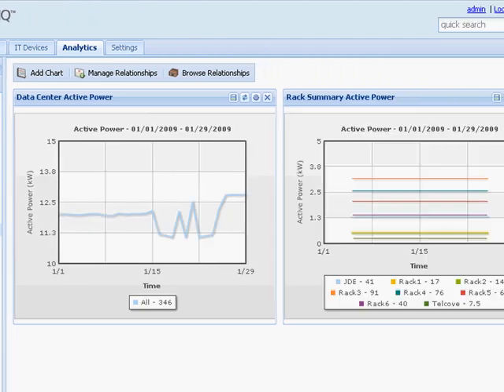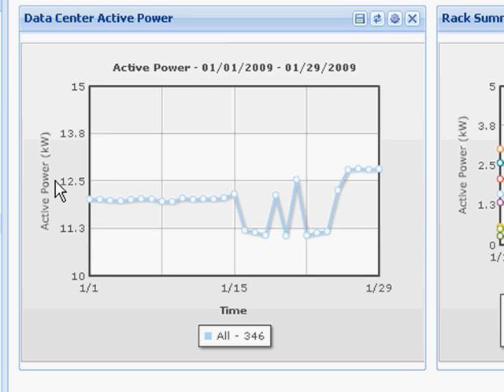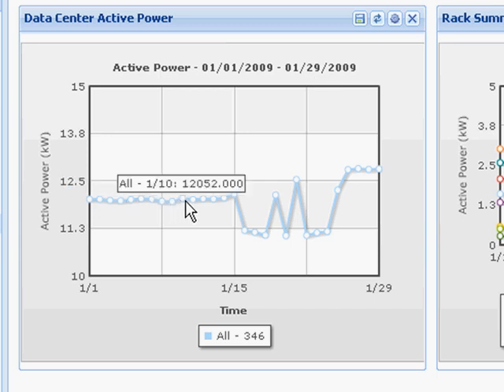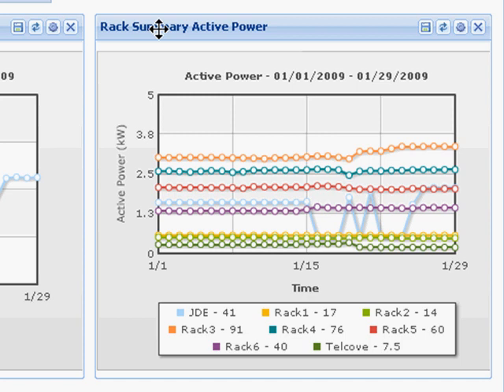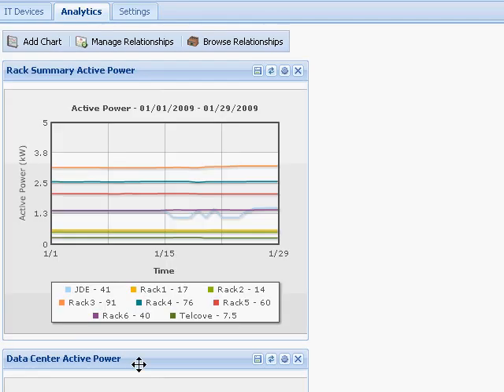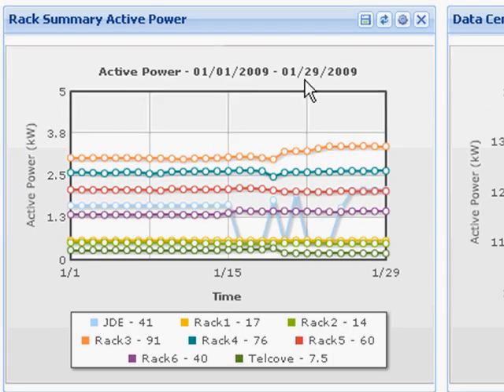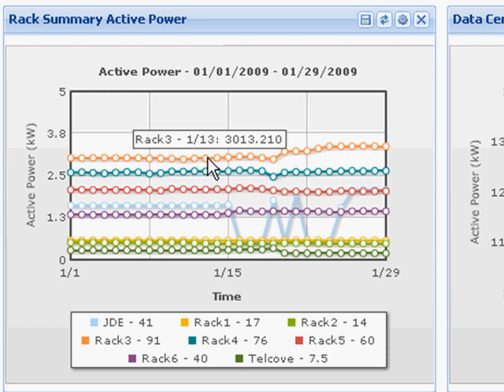I have a summary active power chart, which provides my active power in kilowatts. I've selected a custom date period of January 1st through January 29th, and I have the trend line for all the IT devices in my data center. This next chart, which I can drag and drop for a side-by-side comparison, provides my active power over the selected period for all my racks within my data center, and allows me to easily spot the racks that are using the most power — in this case, rack 3 at 3 kilowatts.